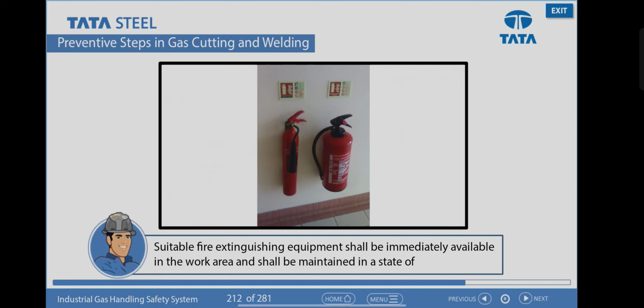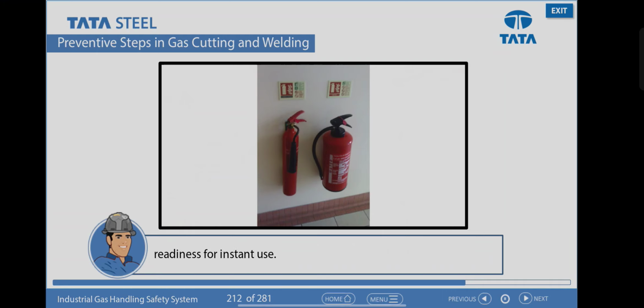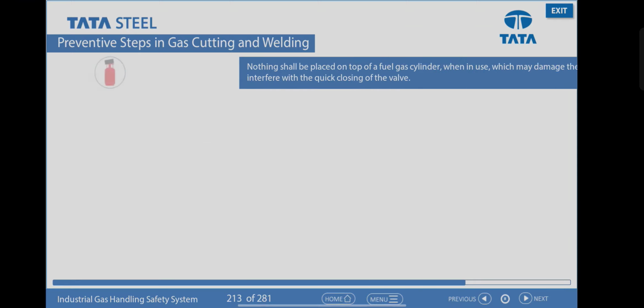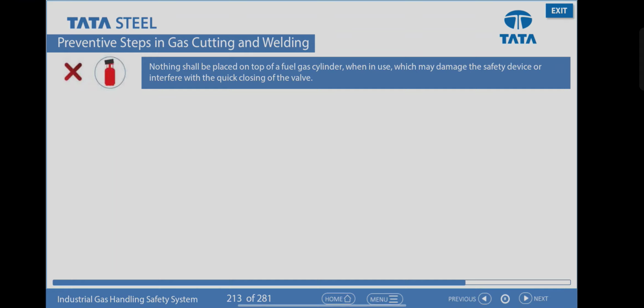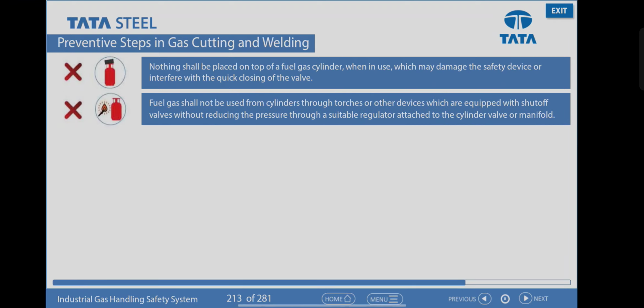Suitable fire extinguishing equipment shall be immediately available in the work area and shall be maintained in a state of readiness for instant use. Use of fuel gas. Nothing shall be placed on top of a fuel gas cylinder when in use, which may damage the safety device or interfere with the quick closing of the valve. Fuel gas shall not be used from cylinders through torches or other devices equipped with shut-off valves without reducing the pressure through a suitable regulator attached to the cylinder valve or manifold.